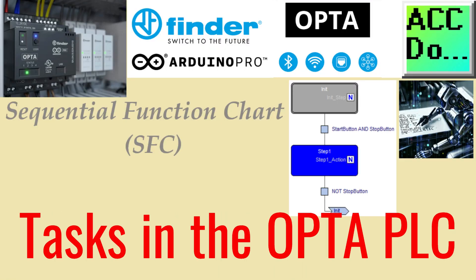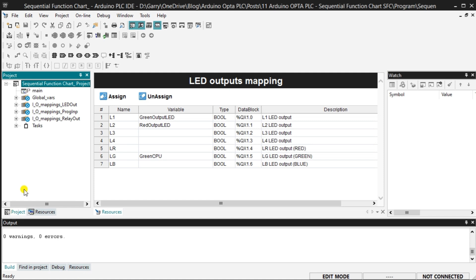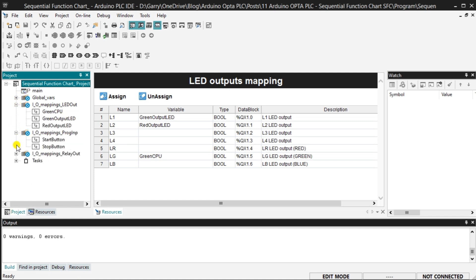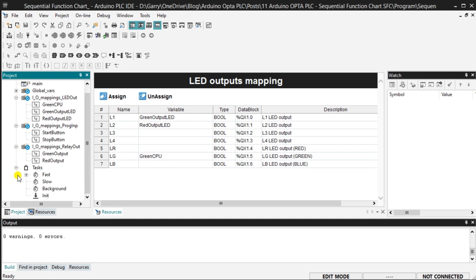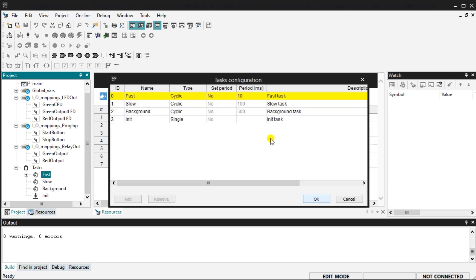To access the tasks in your project, navigate to the project tab and locate the tasks folder. You will see the list of IOs we have just mapped for this project. Expand the folder by clicking on the plus sign next to it. The tasks are categorized into fast, slow, background, and init. To configure the tasks, right-click on any four task folders and select task configuration. Your programs will be executed within the designated task folders.